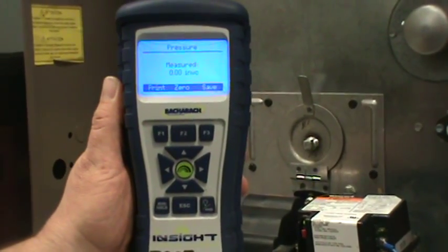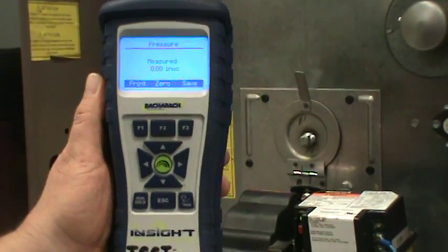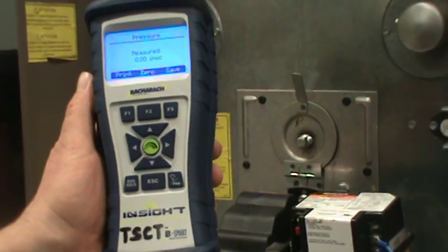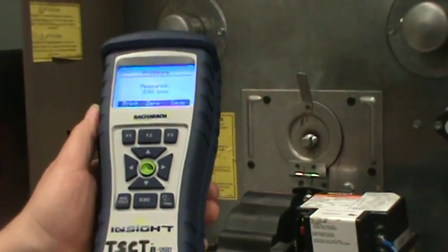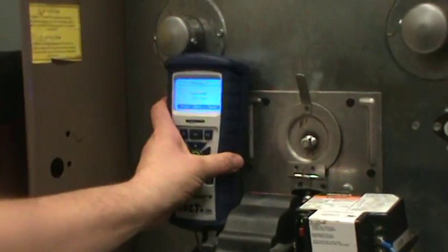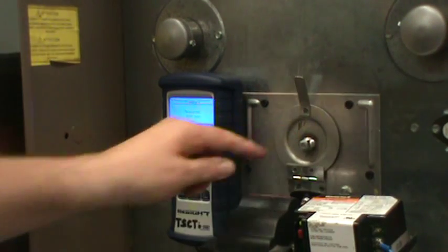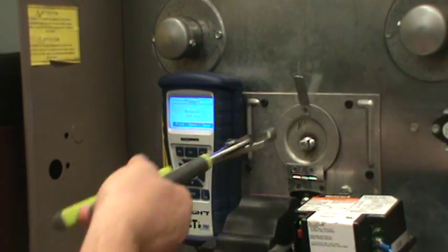We're looking for a negative 0.02 as ideal. Too much overfire draft, we're pulling where it's inefficient. Not enough overfire draft, we're going to have that rumbling, that pulsating going on, that soot creation that we don't want. So I'm going to put my analyzer right here, right over the fire. We have a hole drilled. It's a fairly large hole in this unit for some reason. And I'm going to pull the plug out.